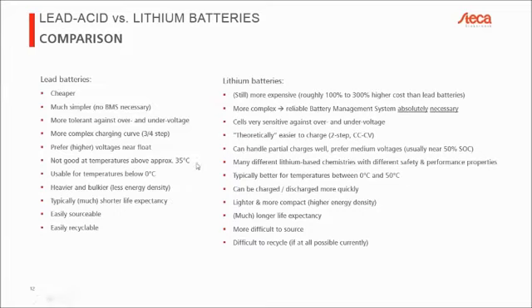Lead batteries are not good at temperatures above 35 degrees. Like I said, it really drastically reduces their life expectancy. There's actually many lithium chemistries which are fine up to about 50 degrees, some even higher, but then they start deteriorating as well. So you can't say that lithium batteries are good for very high temperatures either, but in a lot of countries in Africa, for example, or around the equator, where you have ambient temperatures around 35, maybe 40 degrees, yes, then typically lithium batteries are the better choice, and they will last much longer than lead.